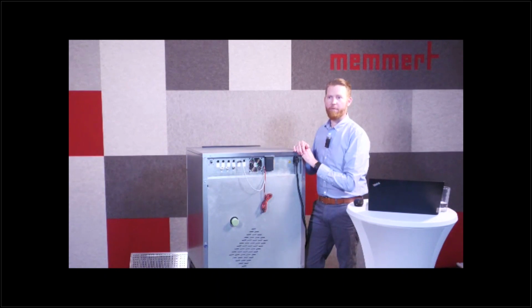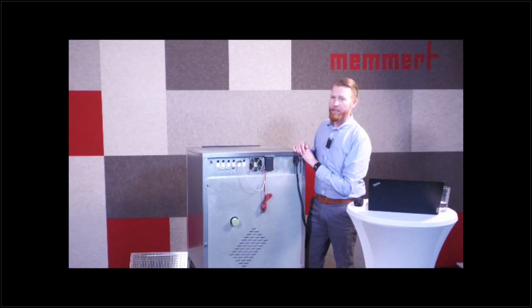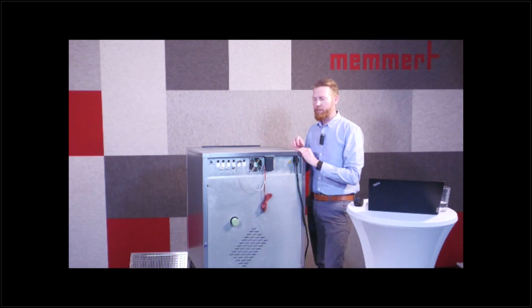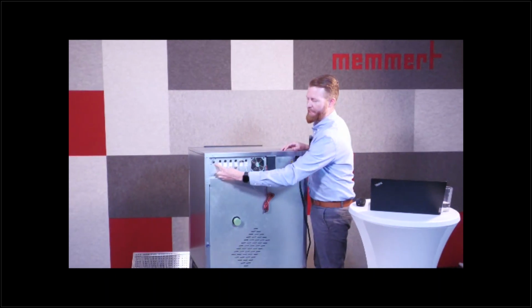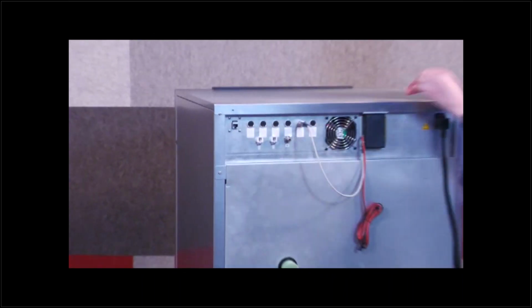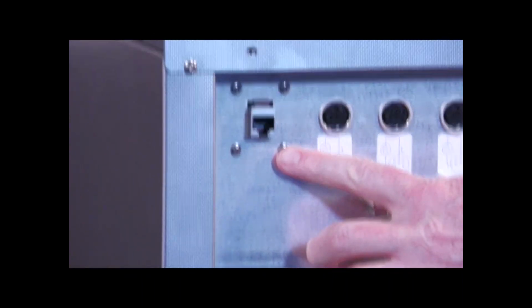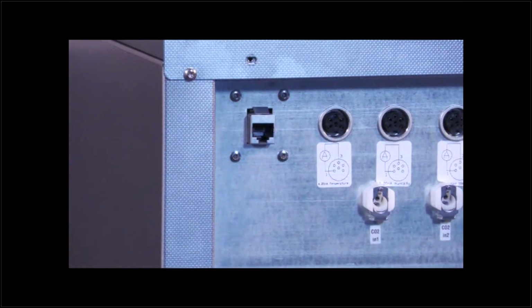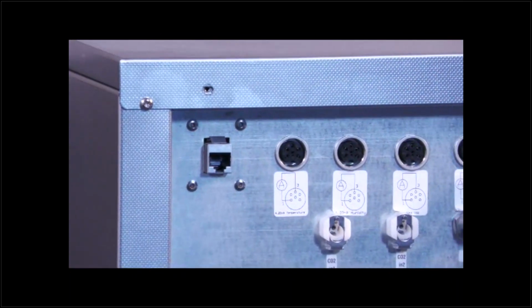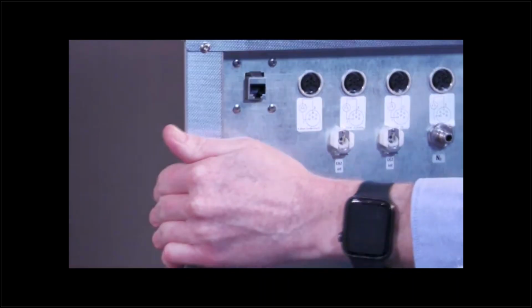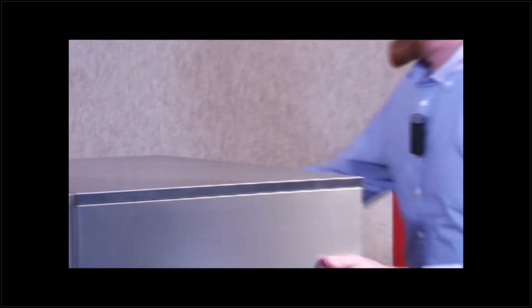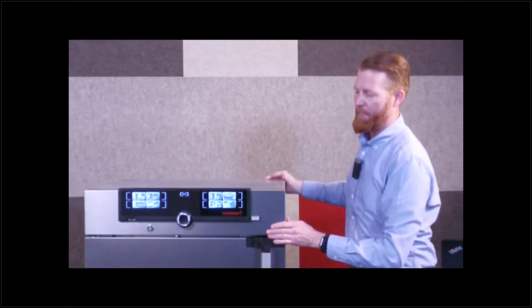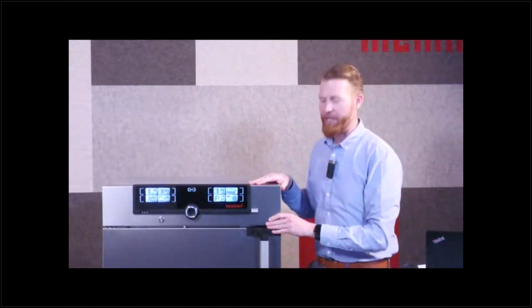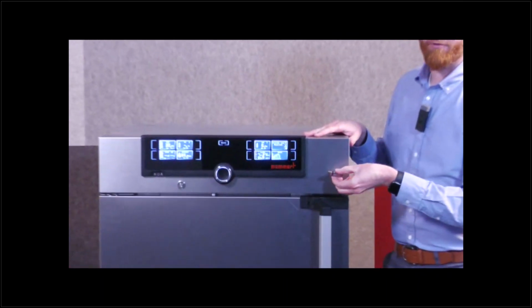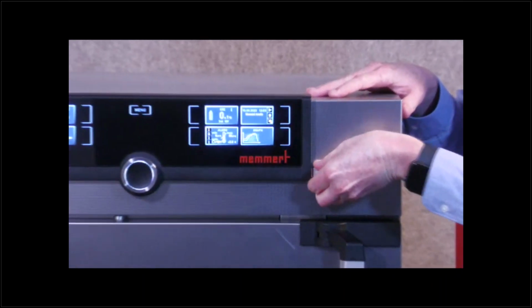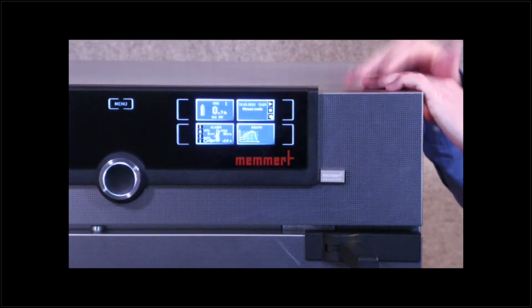And one point which is important, when it comes again to reading out the logged data, is the interface here. This is an Ethernet connection, so it should always be very easy to connect the devices to the local area network to read out the data. For this unit in particular, we also have a second possibility of reading out data very easily, which is a USB interface here at the front panel. So directly on the controller, it is possible to read out data, and this makes it very, very easy.